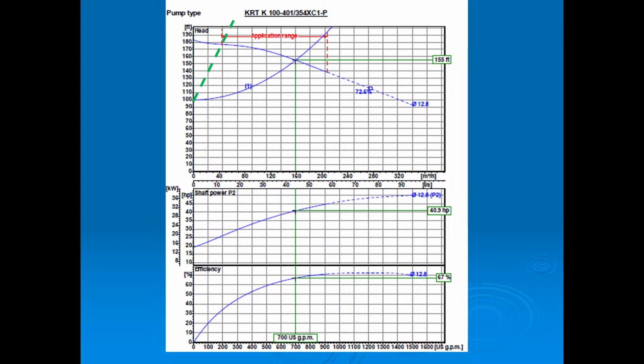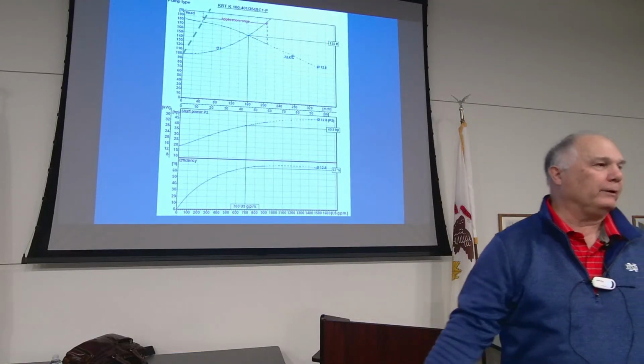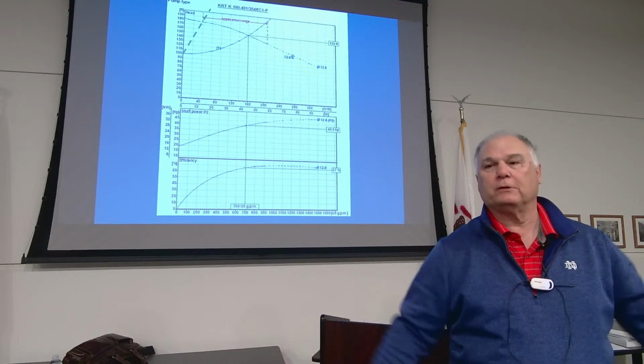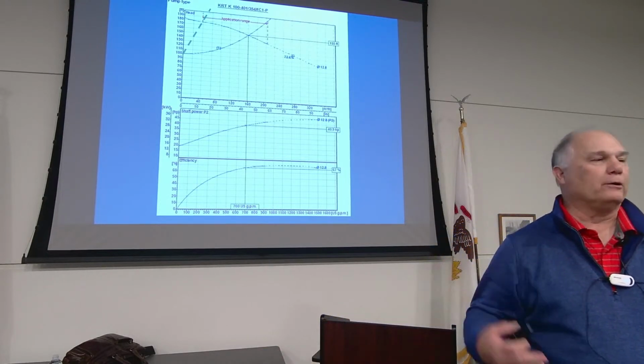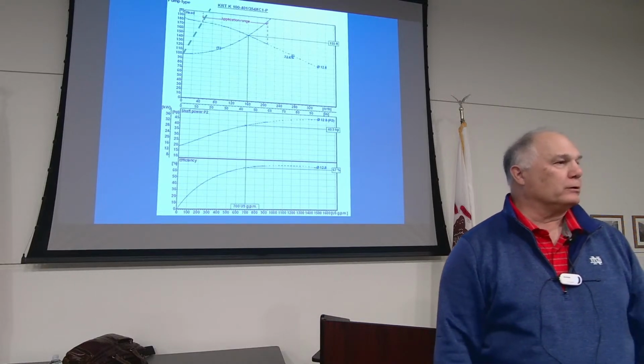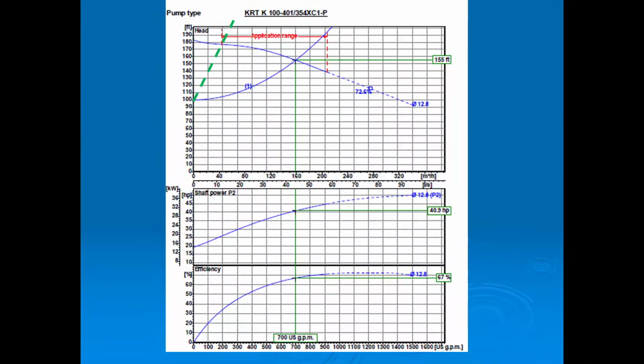So how many PSI is 100 feet? How many feet are equal to 1 PSI? Close. 2.31. So if that's 100 PSI, that would be 231 feet. We aren't going to get 231 feet in our normal conditions for what we do. We're going to be somewhere less than 100 feet, mostly on static, in usual conditions. But why does that blue line go up in a parabola, if you will? It's not straight up at a 45-degree angle. Anybody?